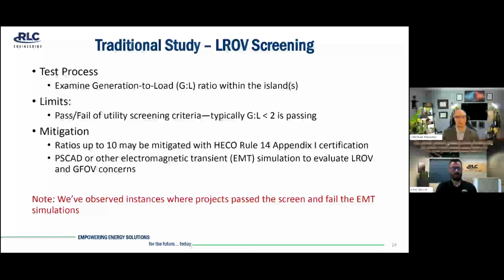Load rejection over voltage. Here, the process is really just looking at the generation to load ratio within the islands. It's usually a pass or fail screening criteria. Most typically, generation to load ratios less than 2 pass or greater than 2 fail. Ratios up to 10 may be mitigated with HECO Rule 14 Appendix I certification. And PSCAD or other EMT simulations can be used to evaluate LROV and GFOV concerns.